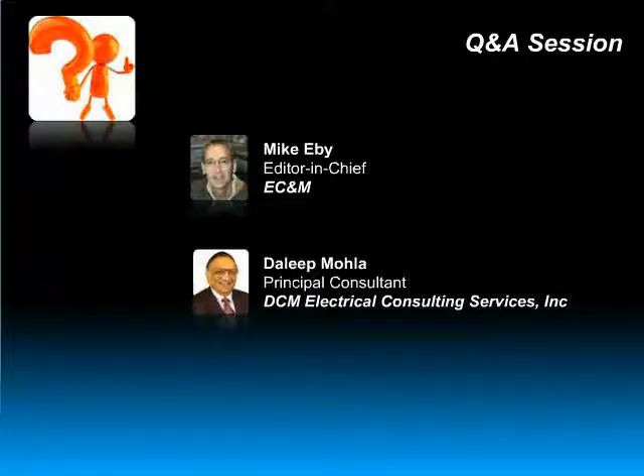Okay. I think we'll ask one more question because this one sounds like it might be a little detailed, and then we're probably going to have to cut it off. So it says, you've explained a maintenance switch, a zone selective switch, and an optical arc detection device to reduce the time to clear the fault. What is the basis of choosing which one you would use according to what type of system you might be in? Okay. There is one difference. Maintenance switch is manually operated. Zone selective interlocking and optical detection are automatically operated.